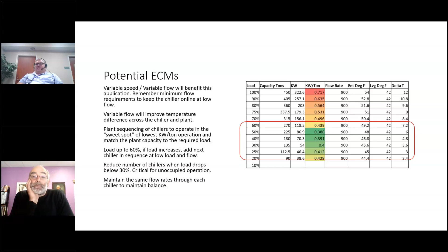So that's where your affinity laws come in, and then you have to verify in the field. If you have the ability to change the flow through the machine, you can put a kW meter on there and actually calculate your performance kW at different flow rates. That's what you end up doing. That's how you verify the performance on this ECM.